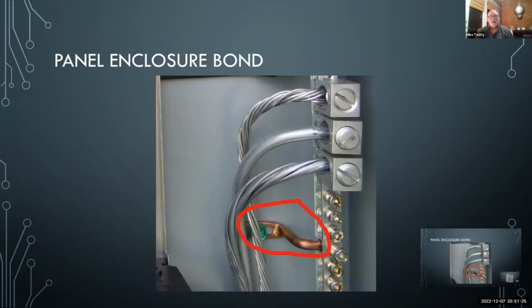Okay, we're going to talk a little bit about bonding here. This is a panel enclosure bond. This is actually service equipment. It's a close-up. You can't tell that, but I remember this. I know what this panel is. This jumper that I've circled is bonding the enclosure, the metal can, the cabinet, and it's bonding the neutral, which is coming into the terminal bar above that you can't see in the picture. The service neutral is coming into a top lug there. So it's doing two things. It's bonding the enclosure, and it's bonding the neutral to the enclosure and to these equipment grounding conductors.